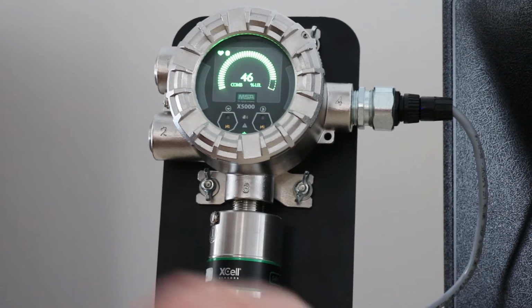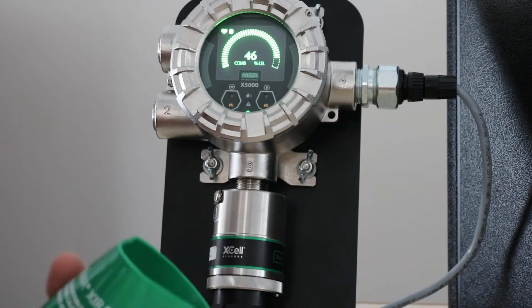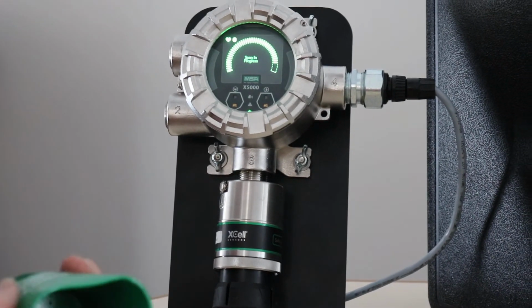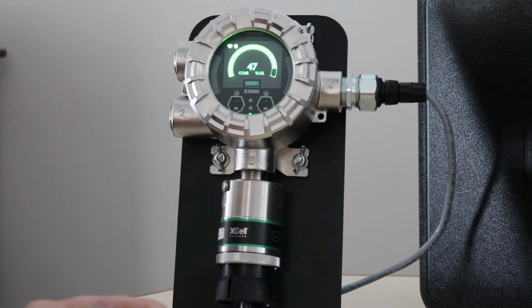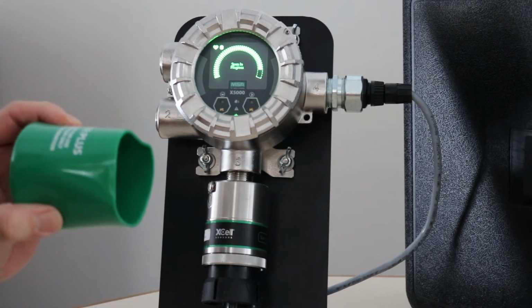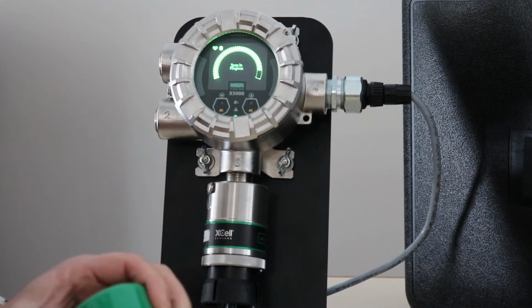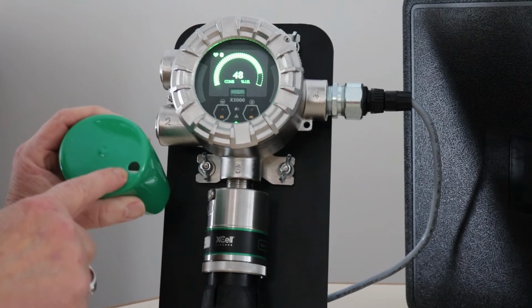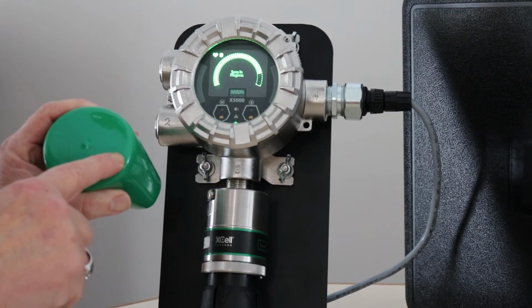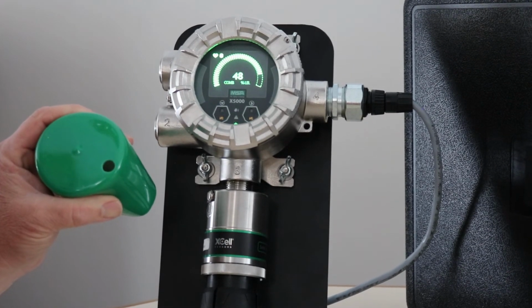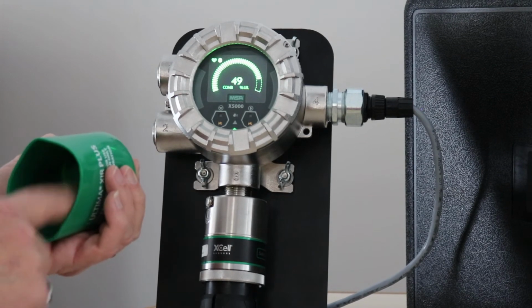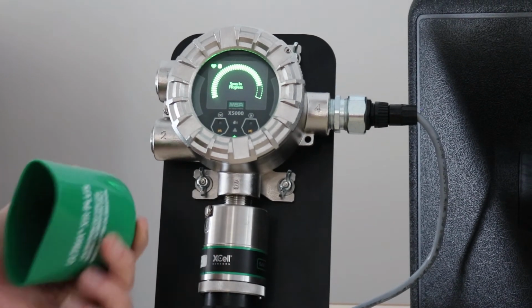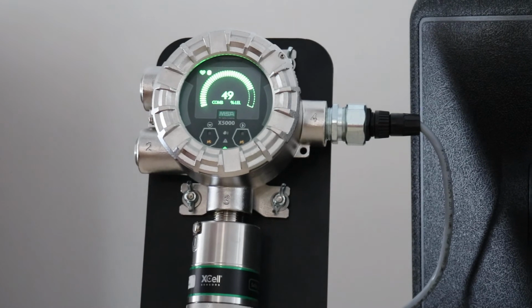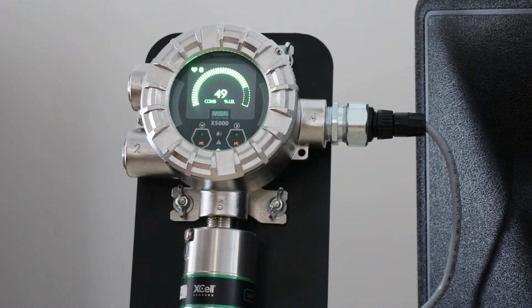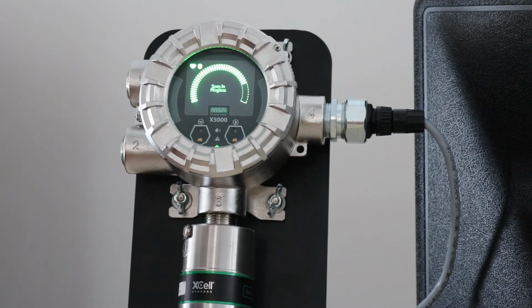Now I'll finish real quick here. Again, this is for the infrared sensor for LELs. And again, your LEL sensor should be mounted horizontally, so it would go on this way. And there is the hole for the calibration tubing and the little knob that comes out. And again, this blocks the wind from blowing out of the sensor. So with that, we will wait for this to settle out.